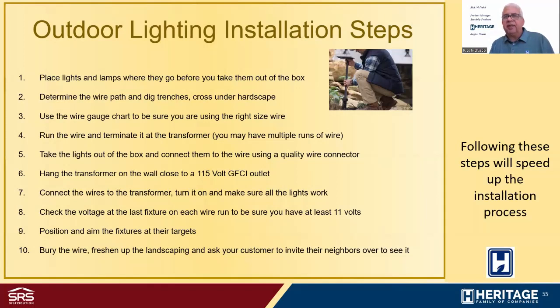And so I recommend you let the system run for about 15 or 20 minutes to make sure all the lights stay on. Sometimes it is possible if you've got a wire cross somewhere on one of the connections, there might be a slow short, and over a period of time, that circuit breaker in the transformer might trip. So give it about 15 to 20 minutes, make sure nothing trips. And that kind of guarantees all your connectors have been done properly.